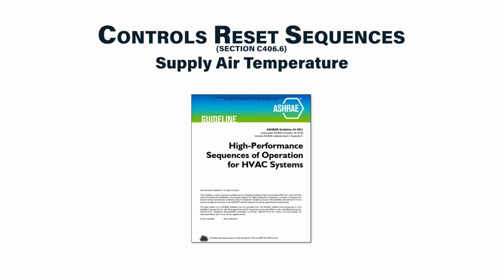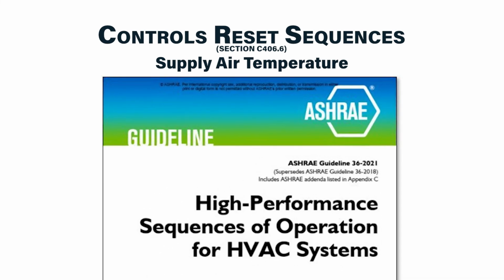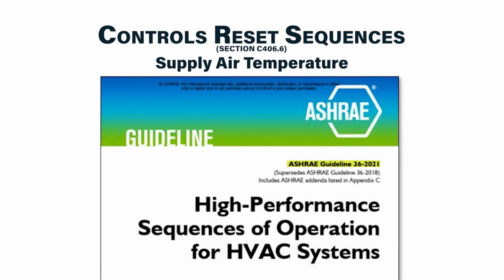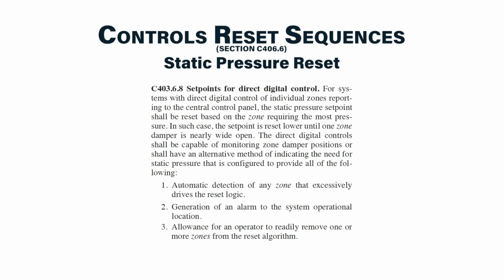ASHRAE Guideline 36 outlines pre-written temperature reset sequences that are based on load, and these are written with input from most major control companies. You can reference these specifications when writing your control sequences. A new requirement in the 2018 code is to use a static pressure reset sequence. This is similar to a temperature reset sequence, but instead with the supply fan.